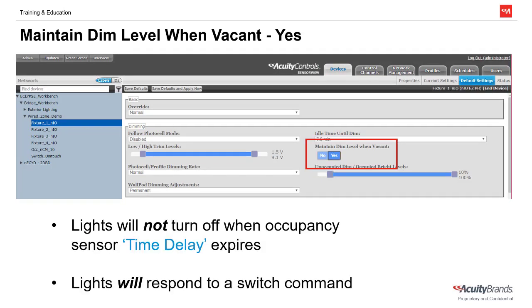If this setting is changed to YES, the lights will no longer be able to turn off when the occupancy sensor's time delay expires. Instead of turning off, output devices set to YES will maintain the unoccupied dim level until the occupancy sensor detects motion again. Note that if an OFF command is issued from a wall pod in the same control zone, those fixtures will be allowed to turn off. Maintain Dim Level When Vacant only applies to when the occupancy sensor expires.